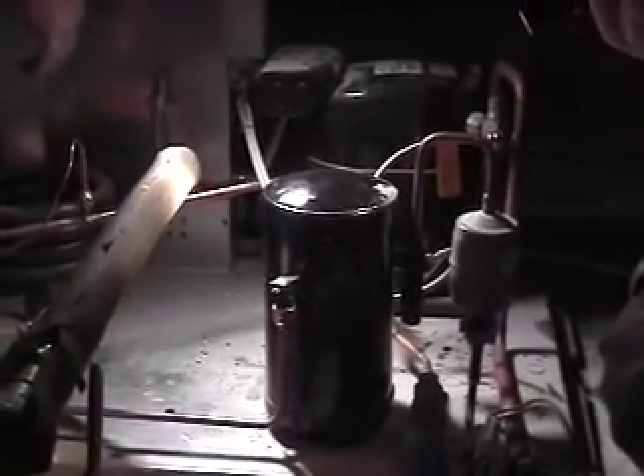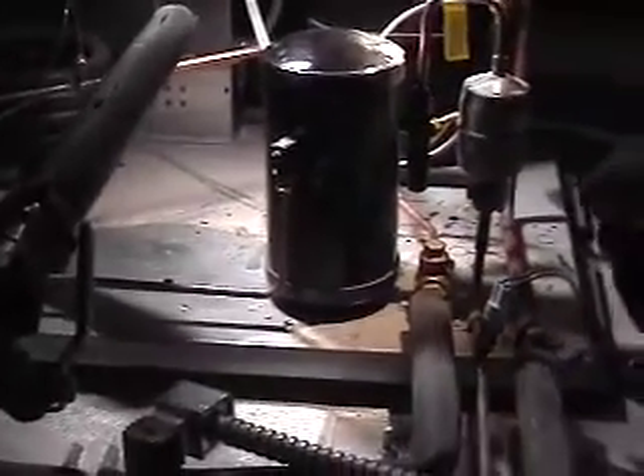Is there anything on the low side? No. No, if it's out of gas, the best way to find out is when you see that. Any questions? Pretty neat system. Yep, very key. The way these things are set up with a hot gas bypass running all the time, they're not starting and stopping all the time. It should last a long time. I've replaced very few compressors.